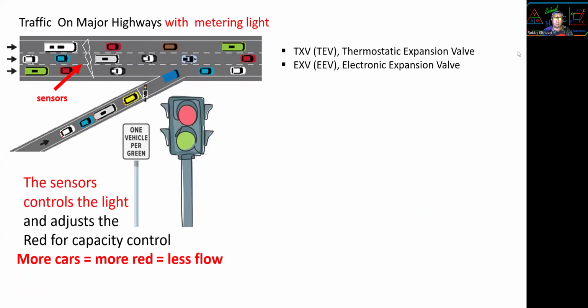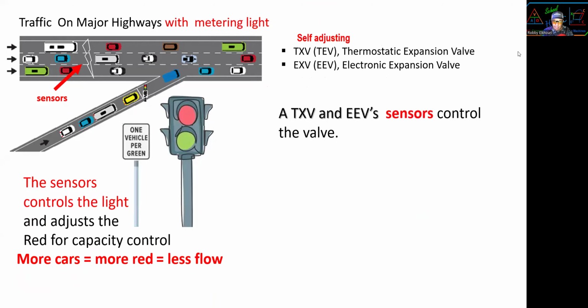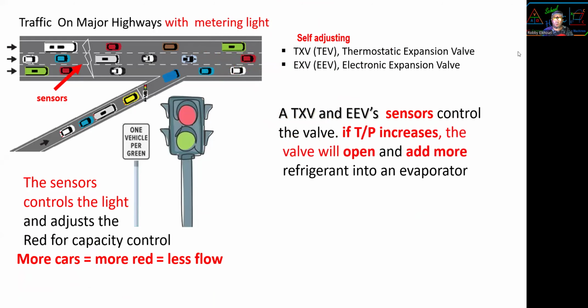TXV and electronic expansion valve, self-adjusting. Sensors control the valve. If temperature or pressure increases, the valve will open and add more refrigerant into the evaporator. Temperature, pressure increase equals open and more refrigerant.